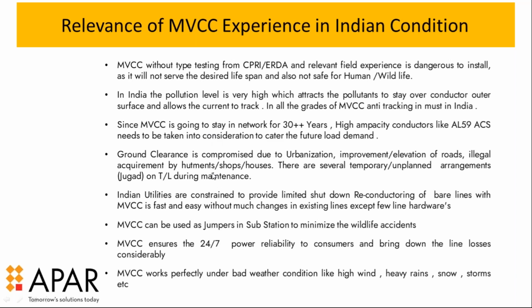Ground clearance is also compromised due to urbanization, improved elevation of the roads, and illegal encroachment of hutments, shops and houses. Many times they are using jugaad, or you can say non-standard practices, to correct the problem. That is not good. Our experience is that if we are prescribing the standards, then the accessories should be properly installed and used on the line as per the standards. No shortcuts or bypass should be used on the lines.